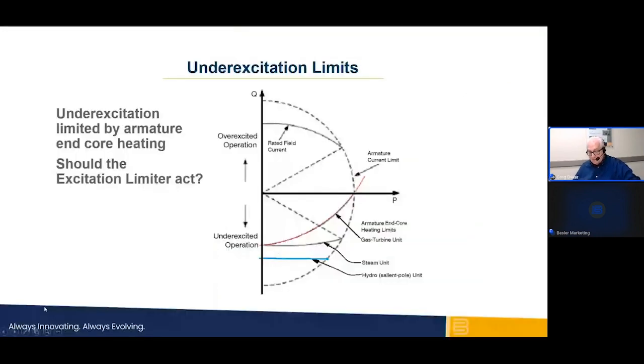The worst control operation for an underexcited synchronous machine is a reduction of field below the level required to maintain synchronism with the utility bus. Remember, what makes a machine a synchronous machine is the rotating magnetic field that links the stator to the rotor. This condition is commonly described as pull-out or out of step, device 78, to protective relay practitioners.